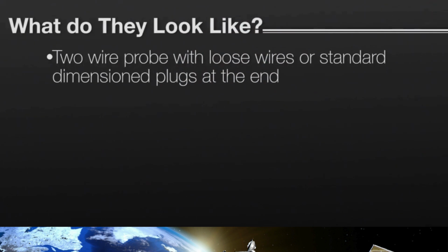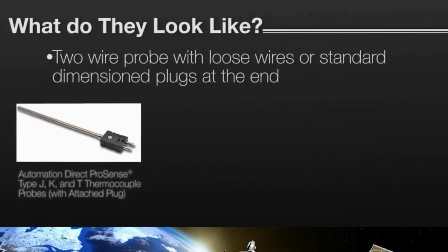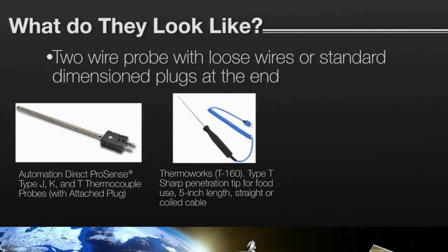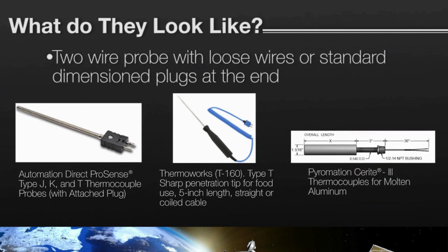I showed you what commercial RTDs look like, so of course, I have to show you what thermocouple probes look like. You can buy them as a straight probe with a connector on the end, like this one on the left from Automation Direct. The penetration probe in the middle of the slide from ThermoWorks is commonly used to measure the temperature of cooked meat in a commercial kitchen. The flexible cable on the end gives the cook more flexibility to move around when using it. The probe on the right from Pyromation is designed to screw into a threaded hole in a furnace. The loose wires on the right would extend outside the furnace to be screwed into a thermocouple connector.